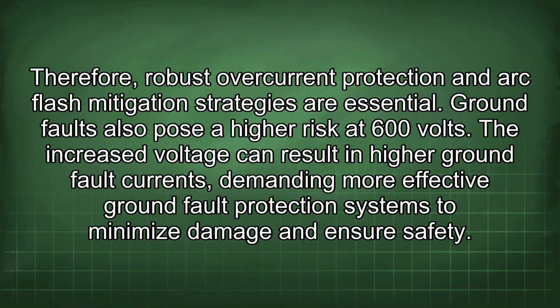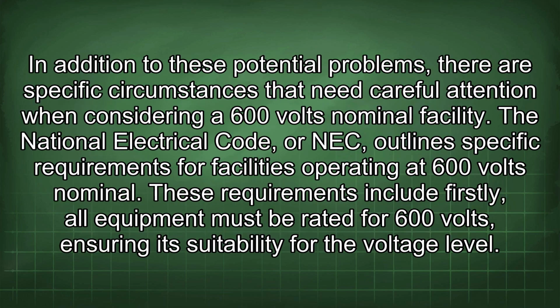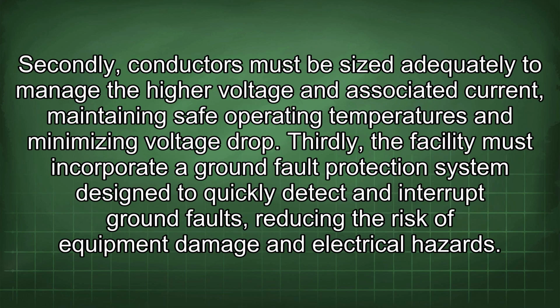and ensure safety. In addition to these potential problems, there are specific circumstances that need careful attention when considering a 600 volts nominal facility. The National Electrical Code, or NEC, outlines specific requirements for facilities operating at 600 volts nominal. These requirements include, firstly, all equipment must be rated for 600 volts, ensuring its suitability for the voltage level.